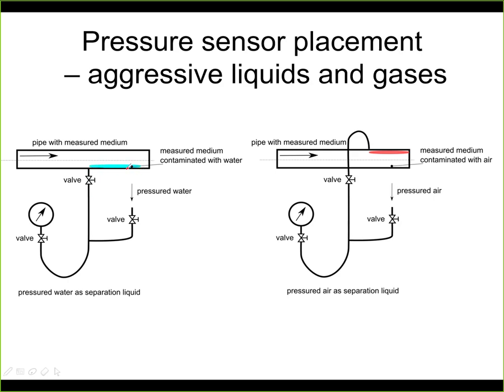But here we feed some pressure water. It leaks a little bit in the pipe, but this whole system is filled at all times. So if this pressure is changing, it will be transferred through the water column here to the gauge, and we will be able to measure the pressure in the pipe. Now note here that this is tapped from the bottom side of the pipe, so that at all times we have water, and eventual bubbles that we may have here in the water may escape like this freely into the pipe. Now if you use air, the installation is almost the same, with one exception over here.